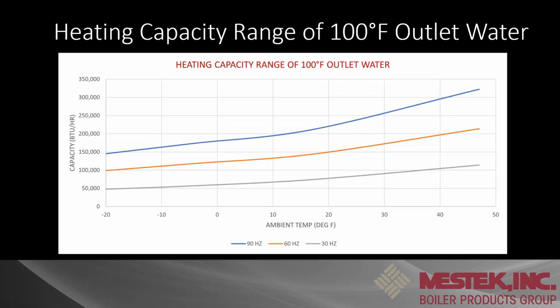Okay, so getting into heating capacities. At this particular slide, I'm showing you the range at 100 degree Fahrenheit outlet water. Capacity in BTUs is on the left, and on the bottom I'm showing you ambient temp in Fahrenheit. Each of these lines, blue being 90 hertz, that's max speed on the compressor, this orangish yellow is 60 hertz, that's mid-range, and the gray being 30 hertz is low fire, low speed.